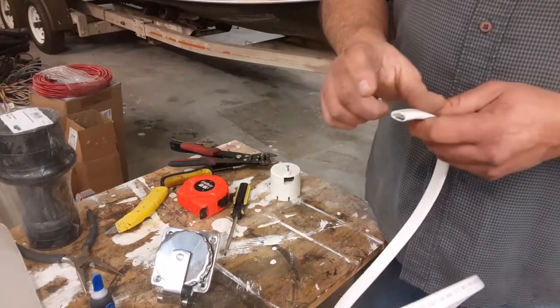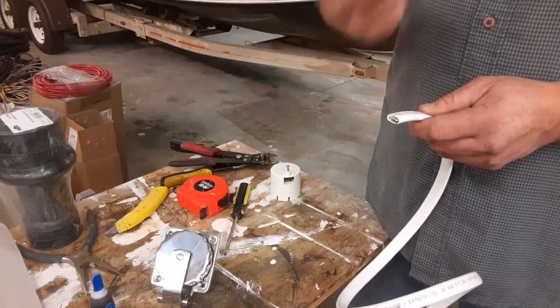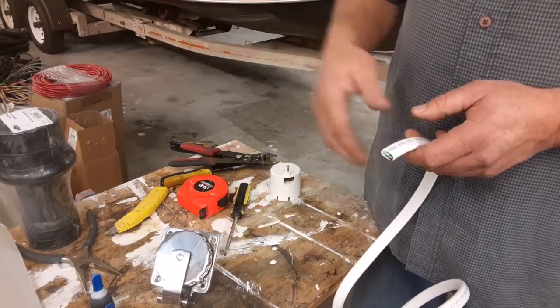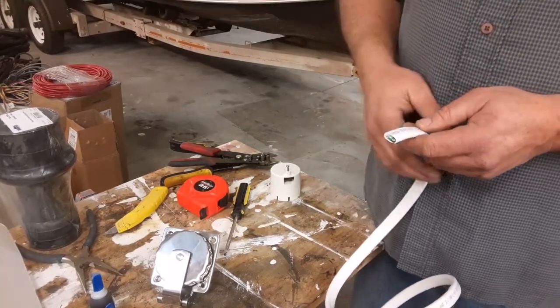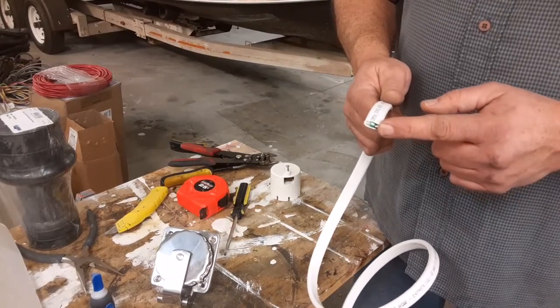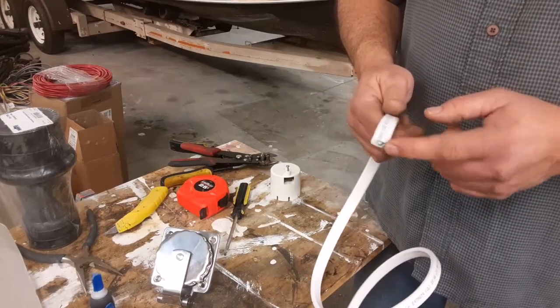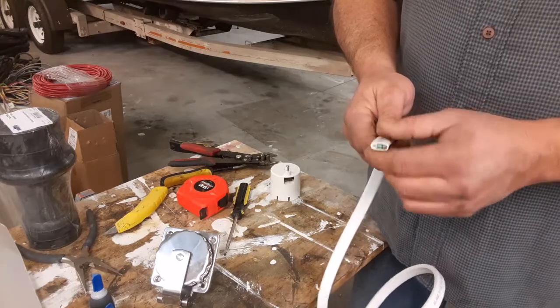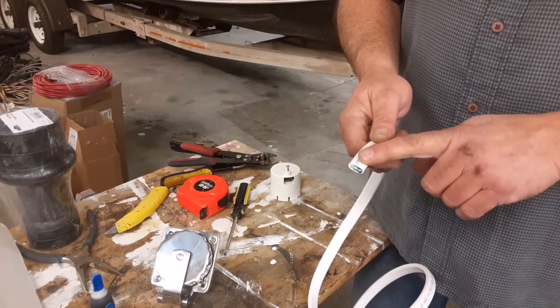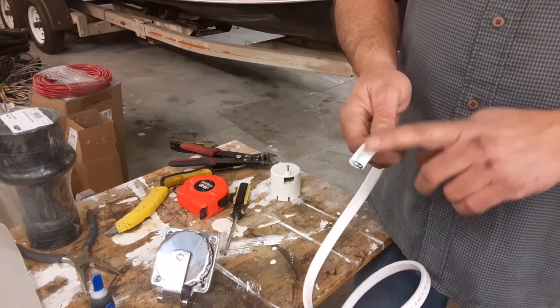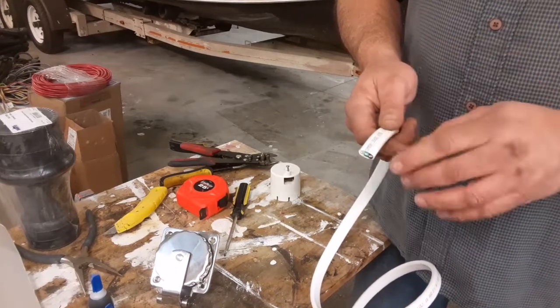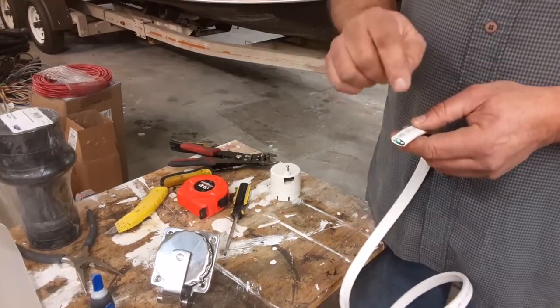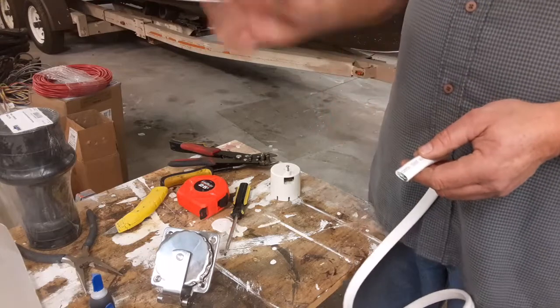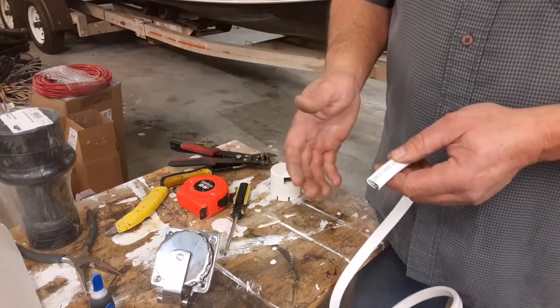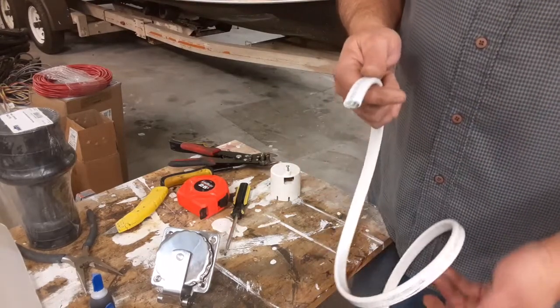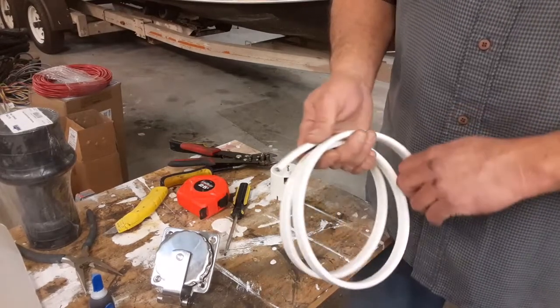The difference between boat wiring and house wiring is two things. Boats move a lot, they vibrate a lot, so this is not solid core wire, it is stranded. The other difference, which you'll see here in a minute when I remove the insulation, is that each strand is individually tinned. It's copper wire that's been tinned, and that's very important - it prevents, or helps prevent, any corrosion in the marine environment.